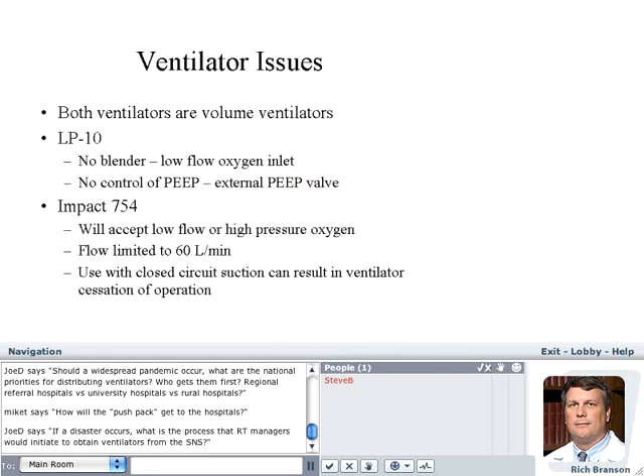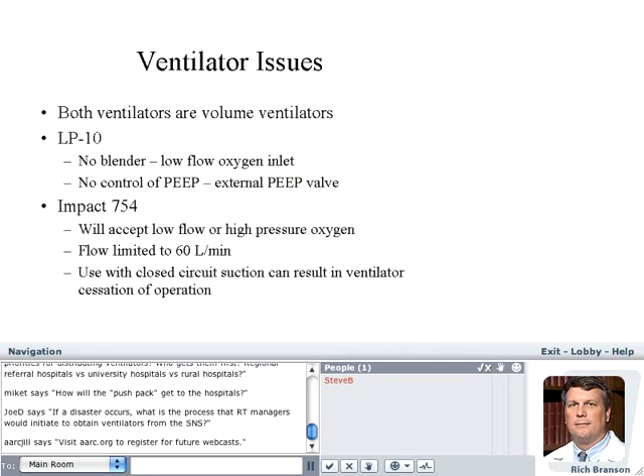There is a low-flow oxygen inlet, and I'm going to show you pictures of the two types. And you don't have control of PEEP, so you'll have to use an external PEEP valve, and then it will become important to set the sensitivity at such a point so the patient can trigger the ventilator. The Impact 754 will take a high-pressure oxygen inlet or low-pressure oxygen, so you can deliver 100% oxygen if you have 50 psi gas. One of the issues that I get into with the 754 is that it only has a maximum flow rate of 60 liters per minute.